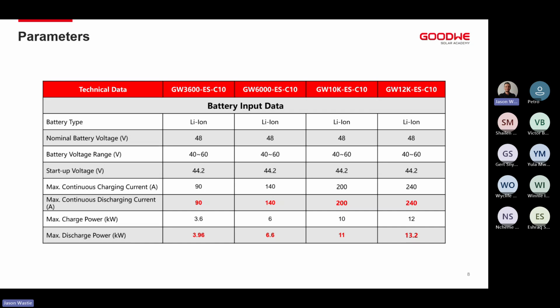Going back to the battery input data, maximum continuous discharging current. This is obviously very much dependent on 2 things: 1, the nameplate capacity of the inverter, and 2, how strong or how powerful your batteries are, whether or not the battery can discharge at that rate. So on the 12 kilowatt unit, we can discharge at 240 amps. Again, like I mentioned, obviously battery dependent.